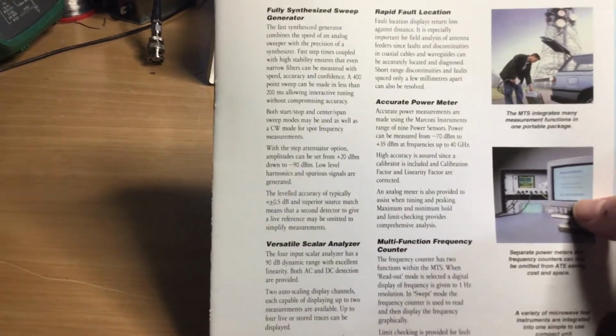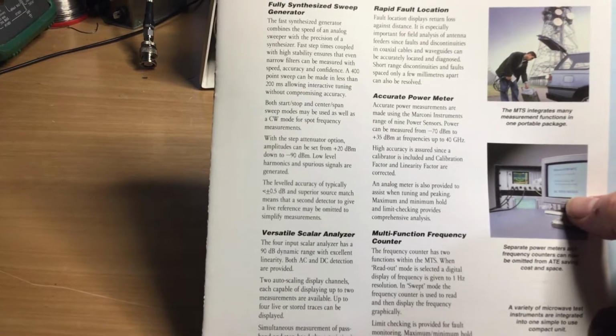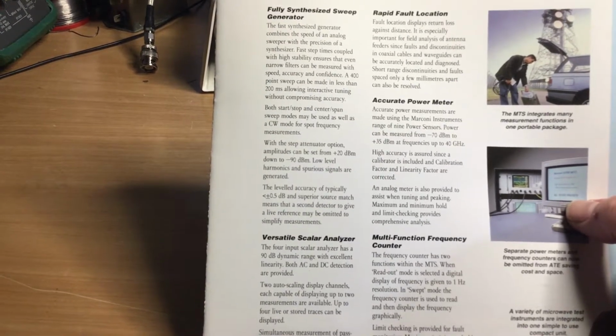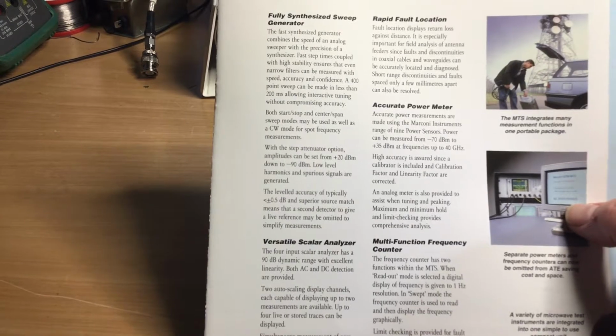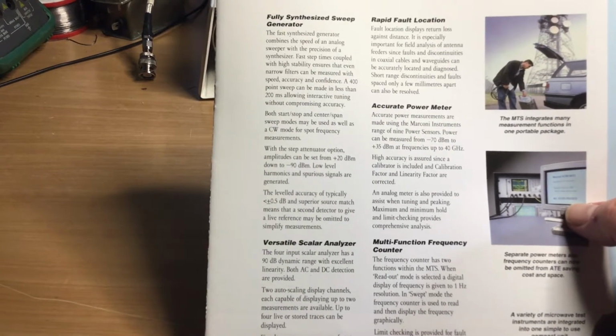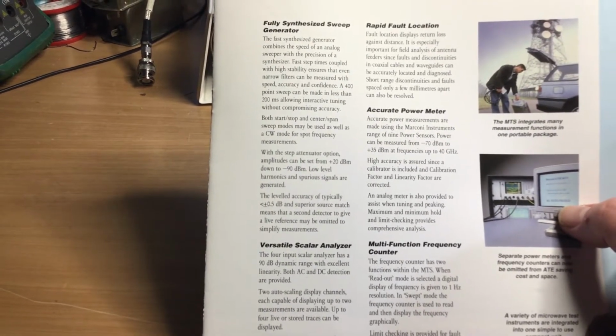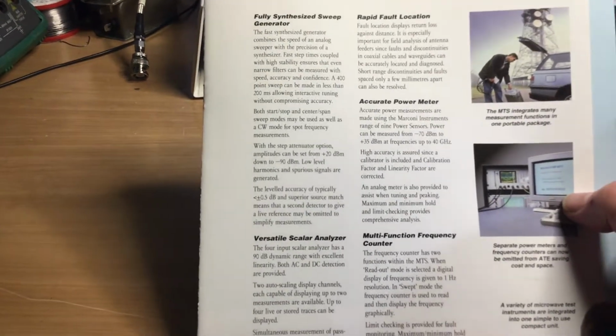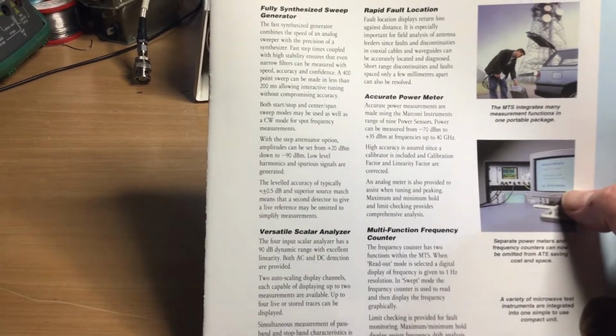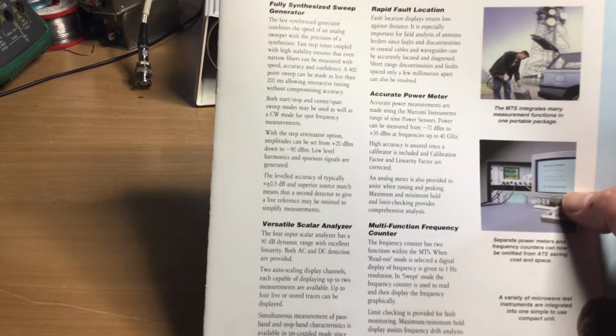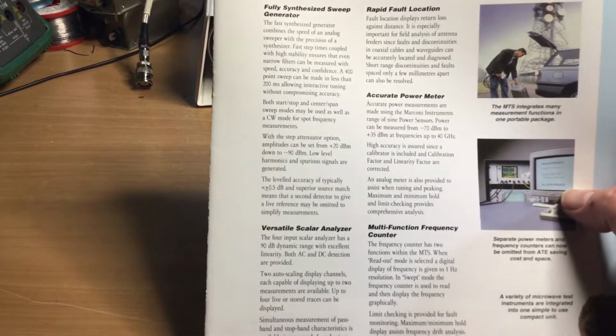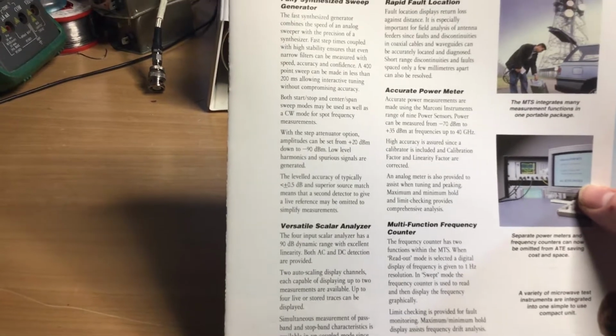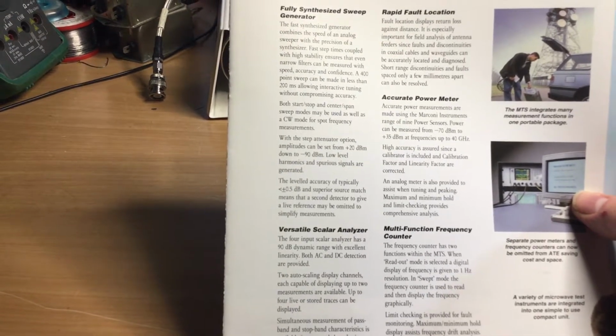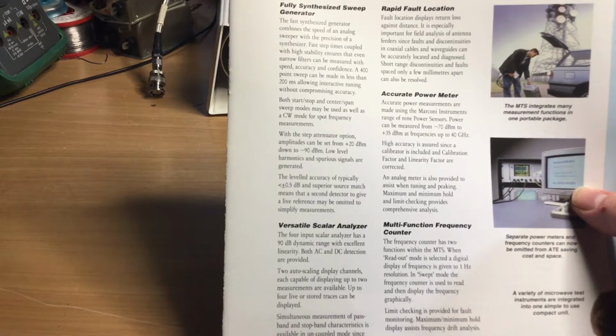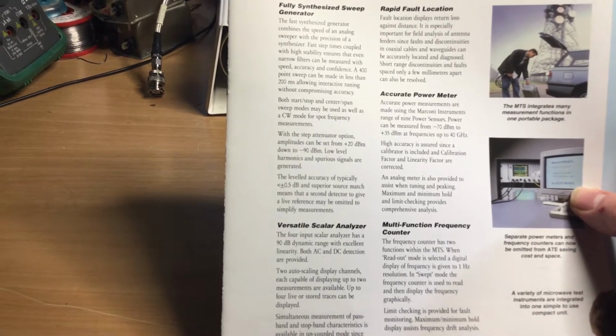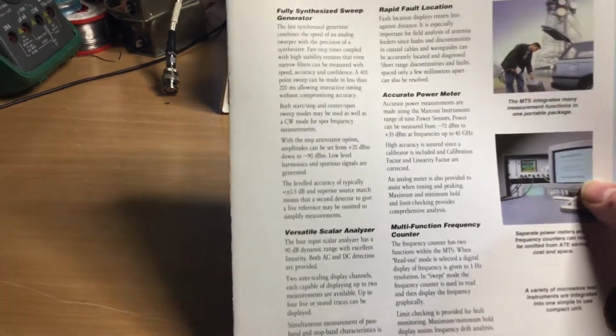It's got an accurate power meter, which means it can do power measurements made using the Marconi instruments range of 9 power sensors. Power can be measured from minus 70 dBm to plus 35 dBm at frequencies up to 40 GHz. It says high accuracy is assured since a calibrator is included and calibration factor and linearity factor are corrected. An analog meter is also provided to assist when tuning and peaking. Minimum and maximum hold and limit checking provides comprehensive analysis.